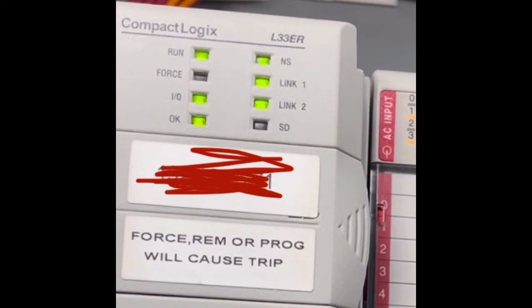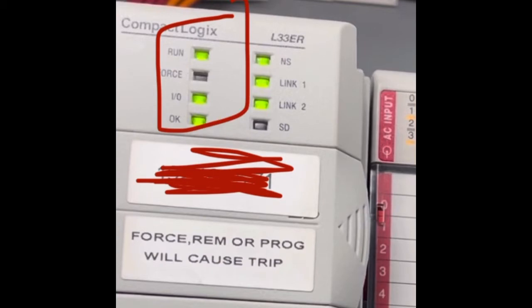On the left hand side here we have the run light. Below that we have the force light and it's off, letting us know that there's no forces in the program, and the IO green light, and the OK light, so everything's good here.